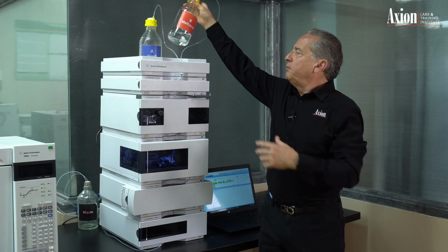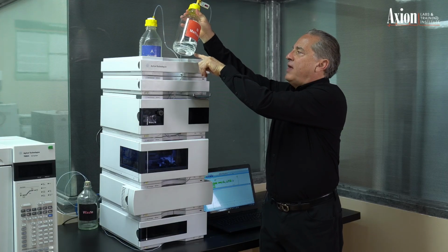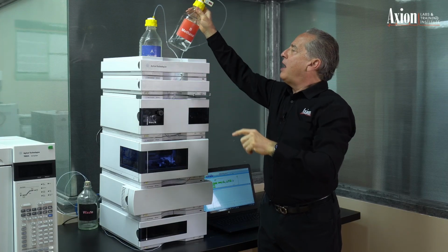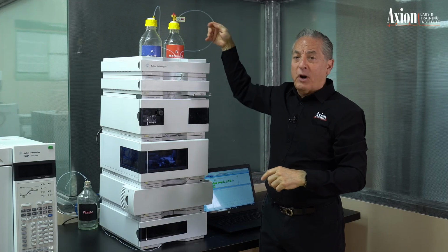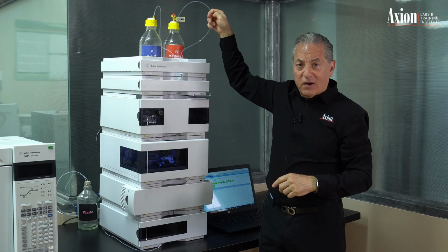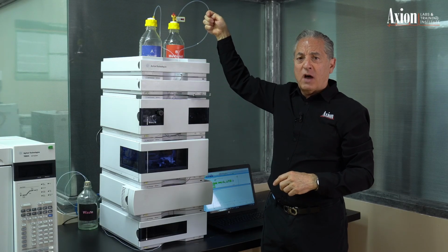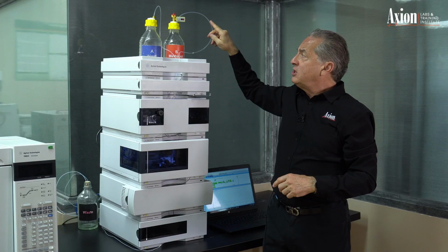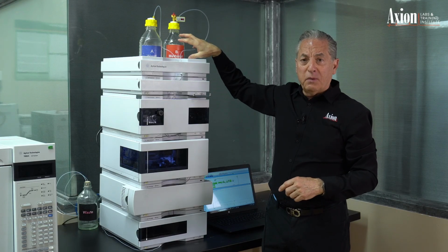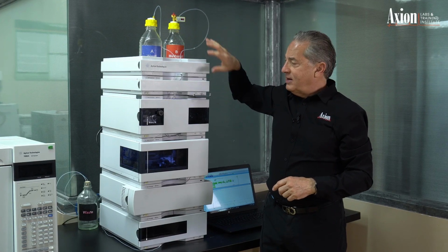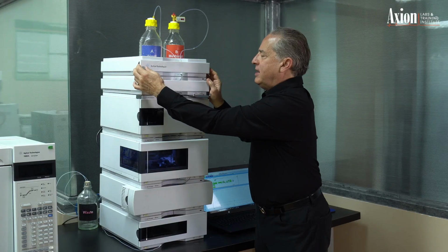So in the bottle, at the bottom, we have our filter, and then coming off the bottle, we have Teflon tubing. So this is low pressure. I could stick my fingernail in there and make an indentation. So this is soft tubing, Teflon, which allows us to transfer the mobile phase from the bottle down to the pump. Now let me take the covers off.